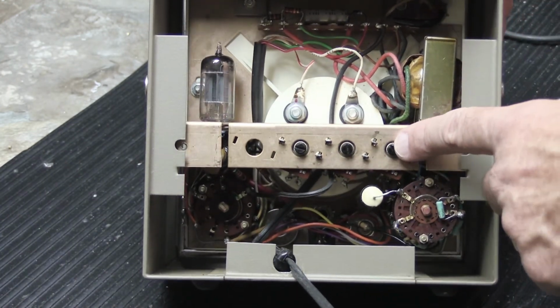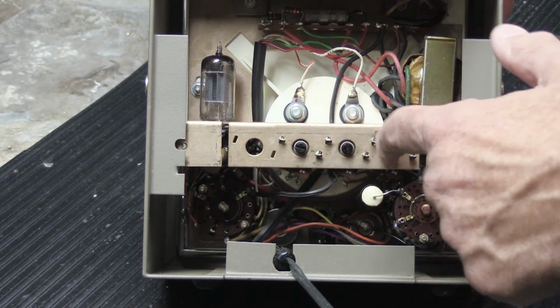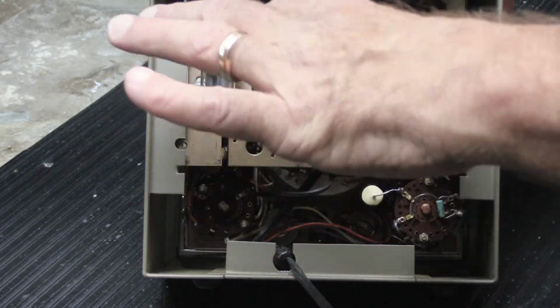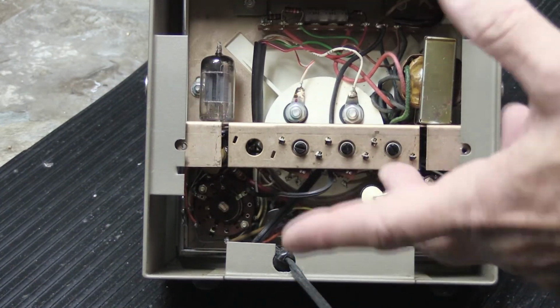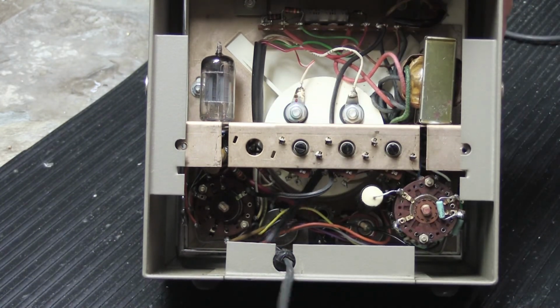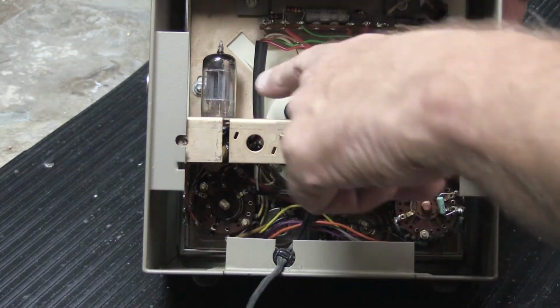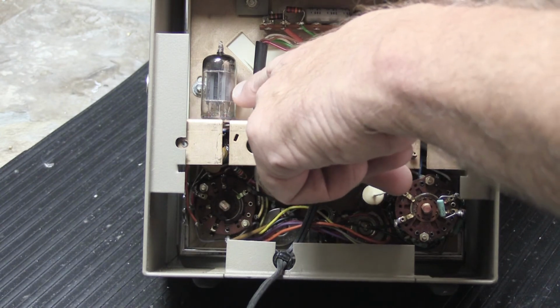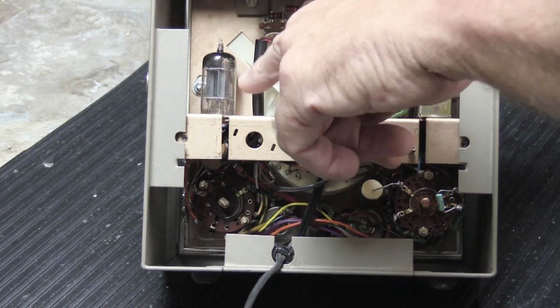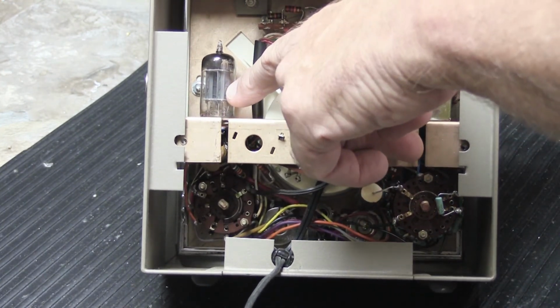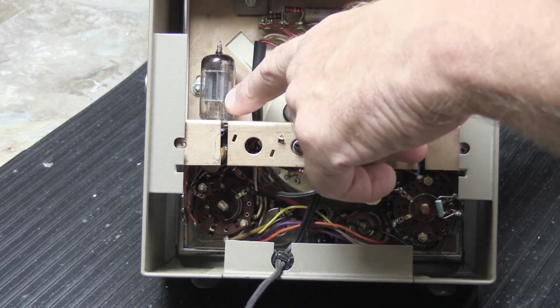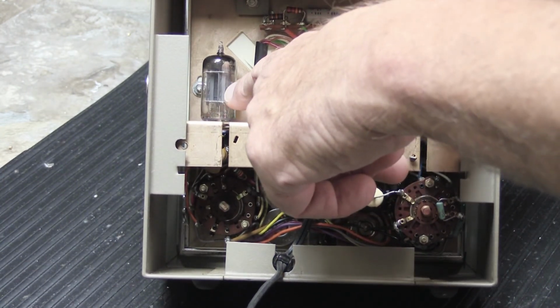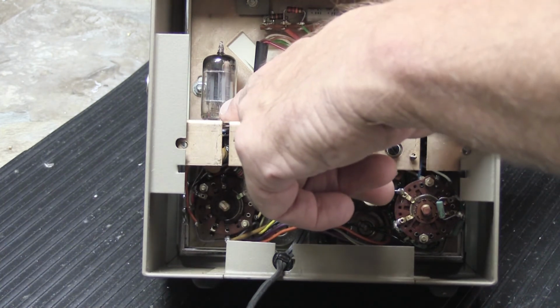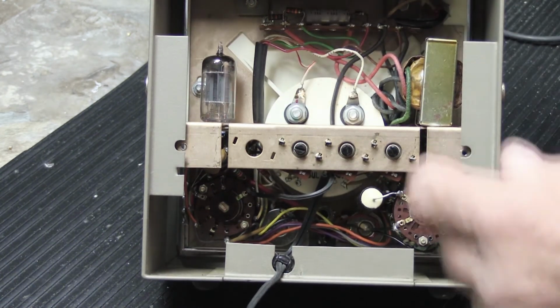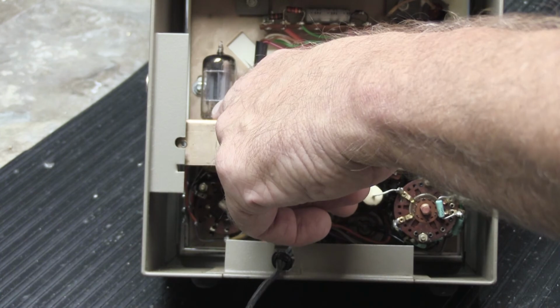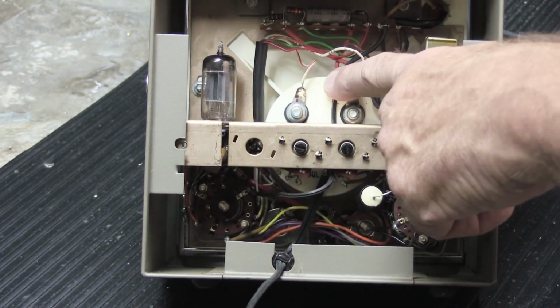These three adjustments here, here, and here, these are alignment adjustments that you measure with a multimeter and then set things up correctly so it reads accurately. And then you have your one vacuum tube here. Those will both be checked, but odds are these are not in a high stress application, so they'll probably be just fine. This is a 12AU7. This is a twin plate triode tube, and its purpose, this is used entirely to drive the meter movement here.